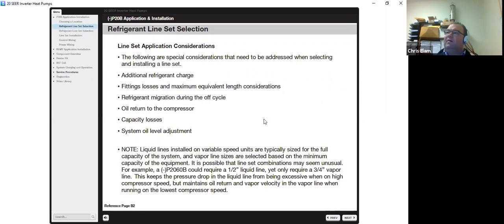It is important to select the correct refrigerant lines, line set application considerations. The following are special considerations that need to be addressed when selecting a line set. Any additional charge that may be required, fitting losses and maximum equivalent length considerations, refrigerant migration during the off cycle, oil return to the compressor, capacity losses, and system oil level adjustment. This is a note: liquid lines installed on the variable speed units are typically sized with the full capacity of the system. Vapor lines are selected based on the minimum capacity for the unit.